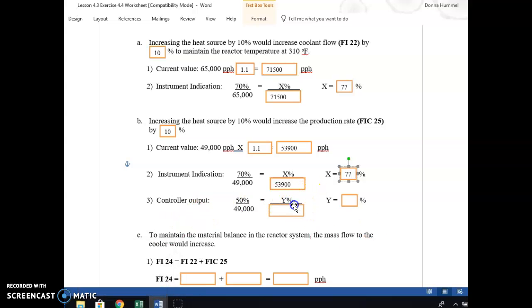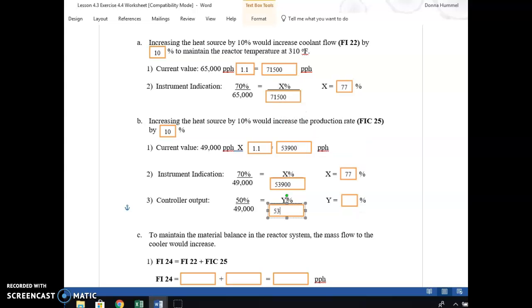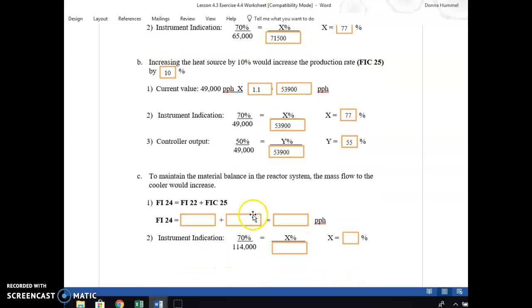Then the output of the controller now, because FIC is a controller, FIC25 is a controller. Normally, it's running a 50% valve opening at 49,000. So at our new number, we're going to put that new number in again, and that's 53,900. So our percentage of our valve opening now, in this particular instance, is 55%. Do that math, check it, make sure you got it.